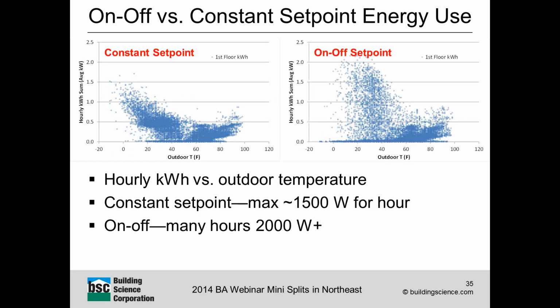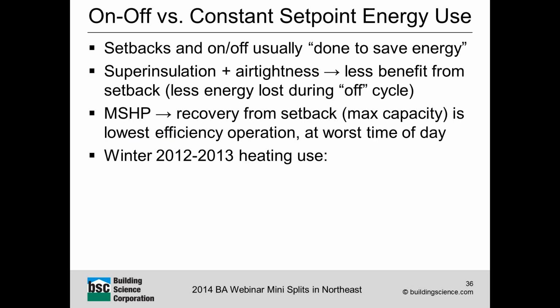I'll just jump over this in terms of time, but one thing I'll point out is that setbacks are usually done to save energy. That's the concept behind it. That being said, if you super insulate a house and make it airtight, the temperature in the house drops very slowly during the off cycle, so there's less benefit from doing the setback. In addition, these mini-split heat pumps operate at their worst efficiency when they're trying to recover from a setback, and it's also typically at the worst time of day, in the morning when it's very cold. So, let's take a look at how the results came out.